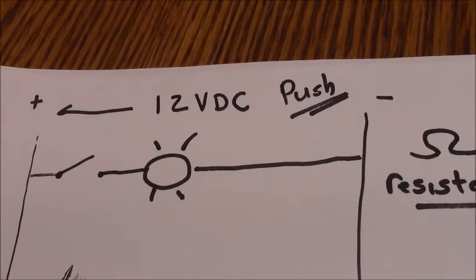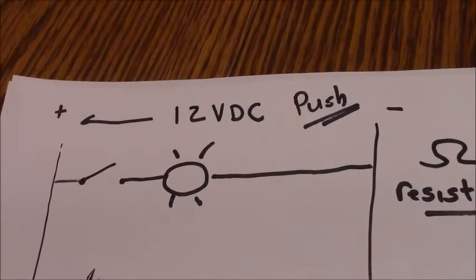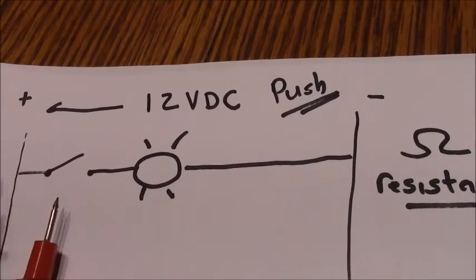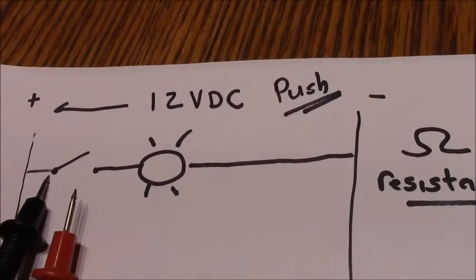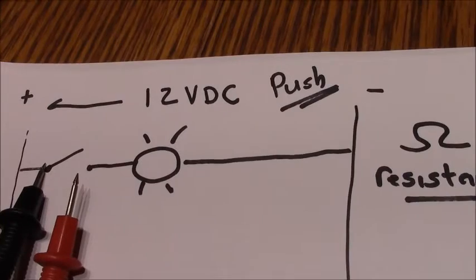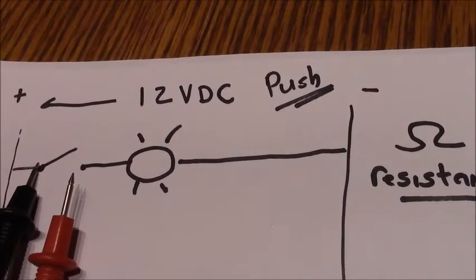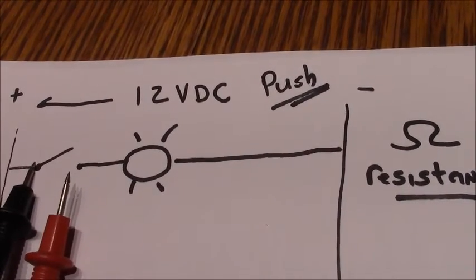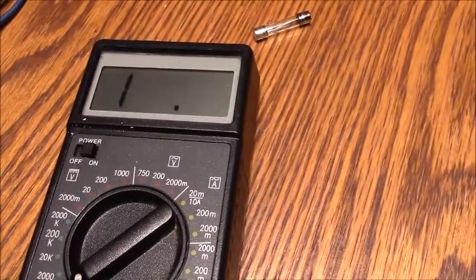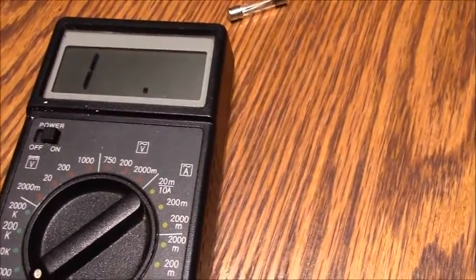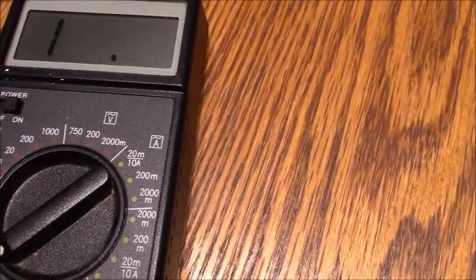So again, what would you check for? You're checking for continuity. If the switch is open, as it is drawn right now, and you take your two probes and place one at each end of the switch, you should have infinite resistance. If you're using a digital multimeter, it will read this funny looking 1, which is infinite resistance.